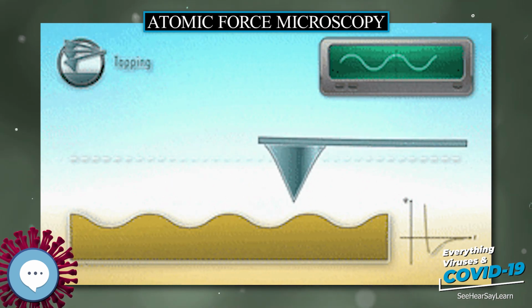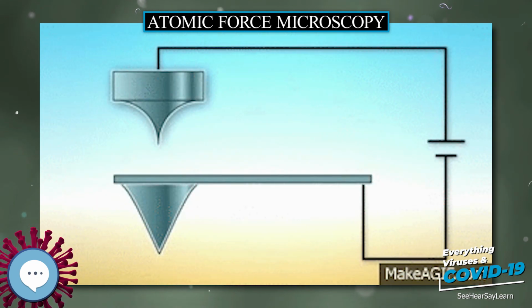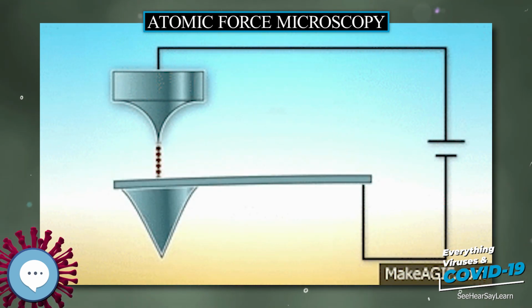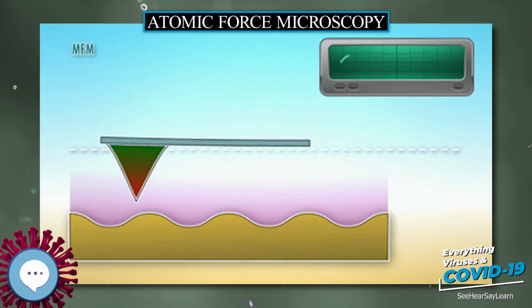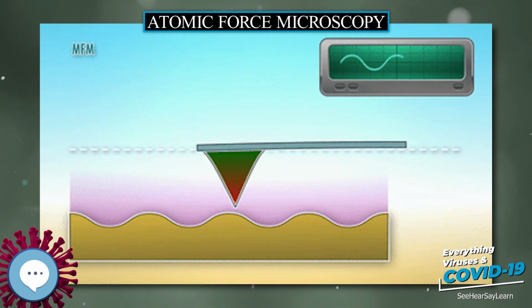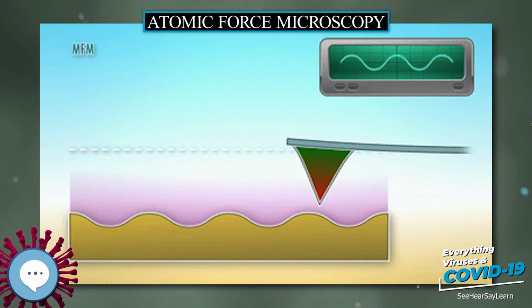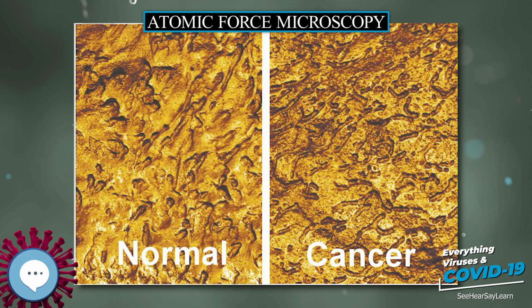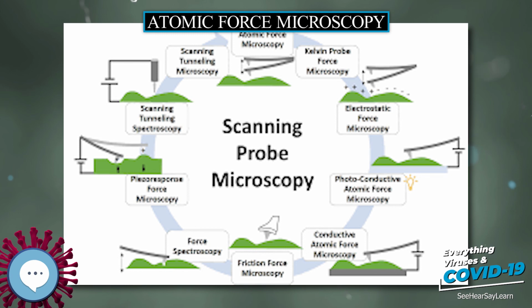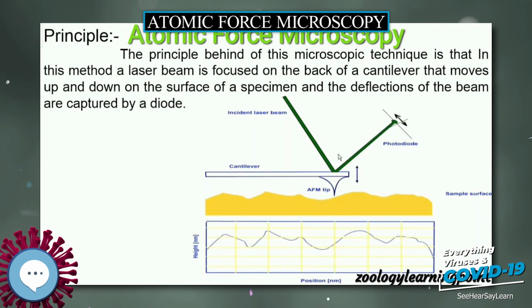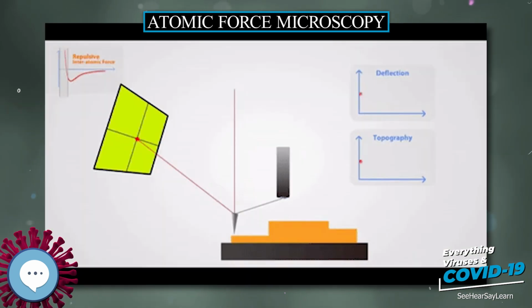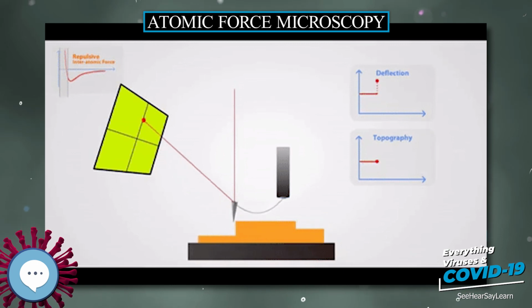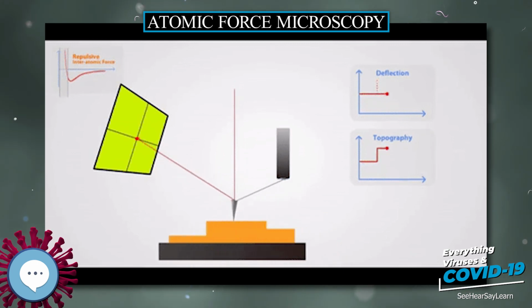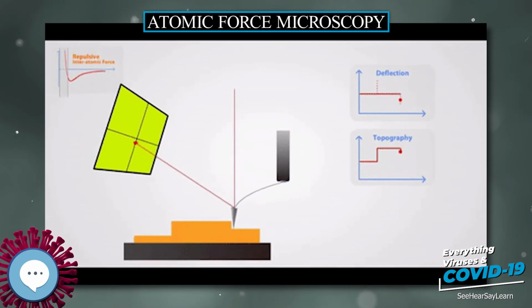This can be corrected by applying a nonlinear voltage to the piezo electrodes to cause linear scanner movement and calibrating the scanner accordingly. One disadvantage of this approach is that it requires recalibration because the precise nonlinear voltage needed to correct nonlinear movement will change as the piezo ages, see below. This problem can be circumvented by adding a linear sensor to the sample stage or piezo stage to detect the true movement of the piezo. Deviations from ideal movement can be detected by the sensor and corrections applied to the piezo drive signal to correct for nonlinear piezo movement. This design is known as a closed-loop AFM. Non-sensored piezo AFMs are referred to as open-loop AFMs.